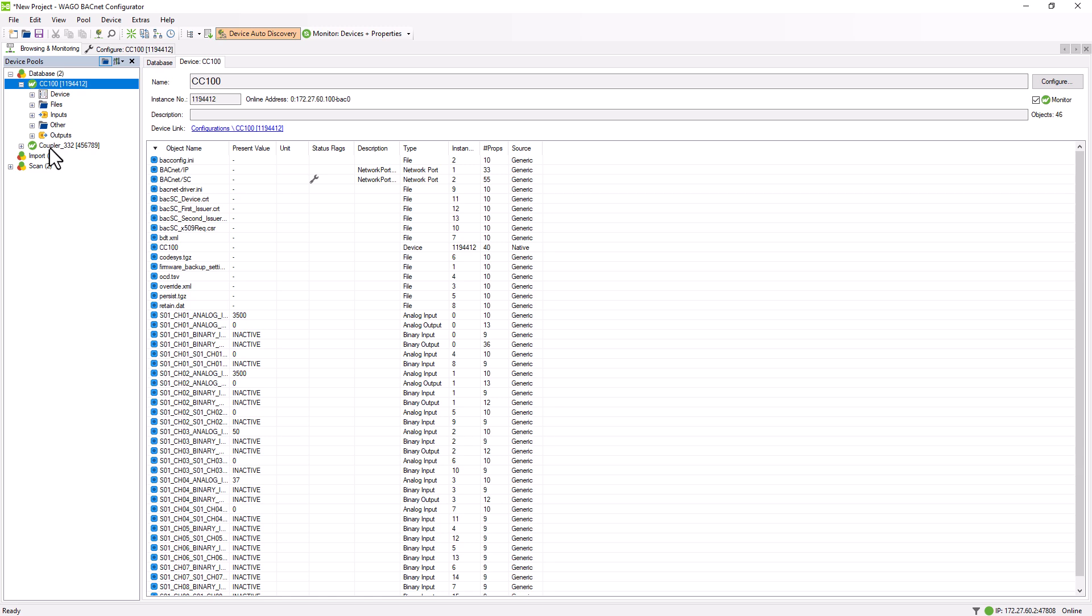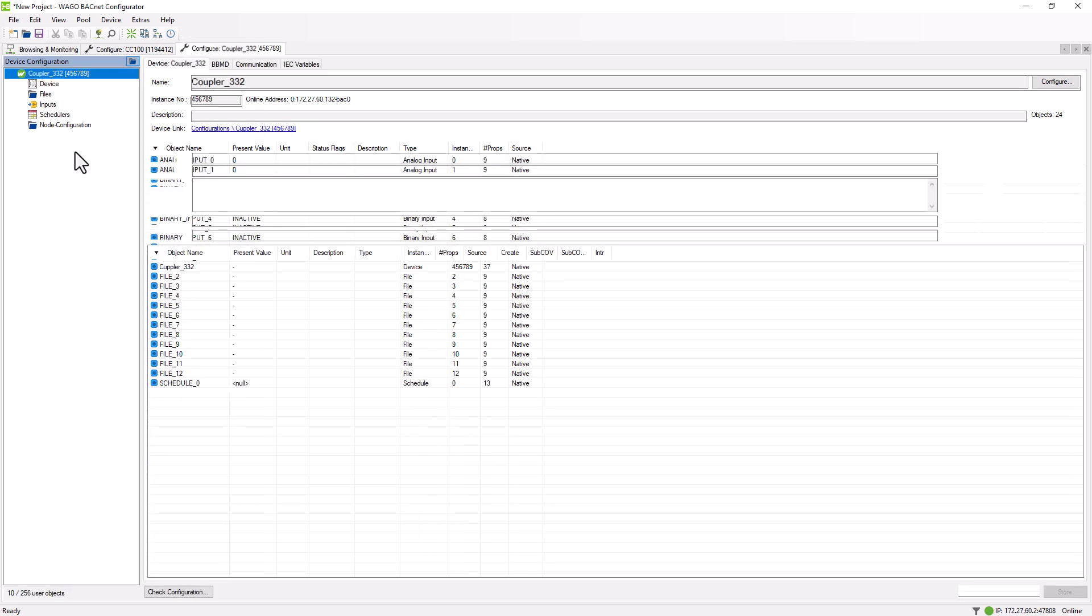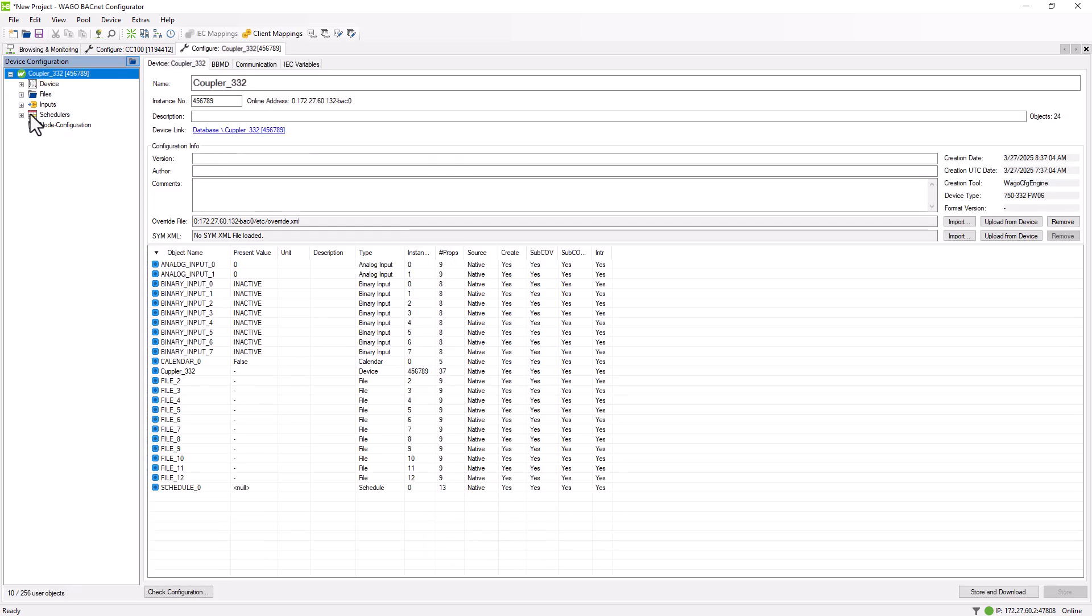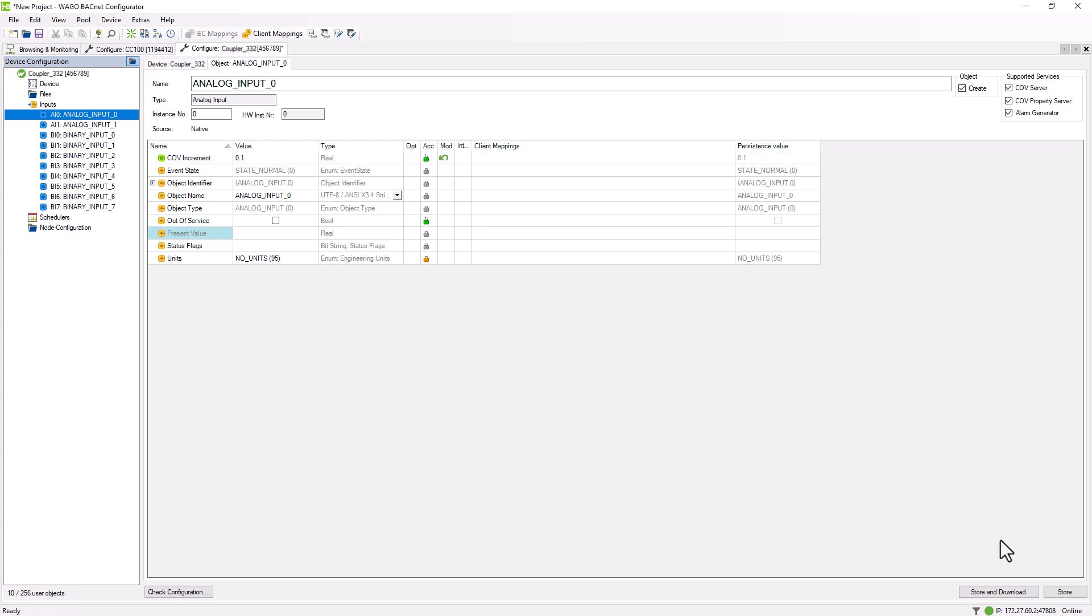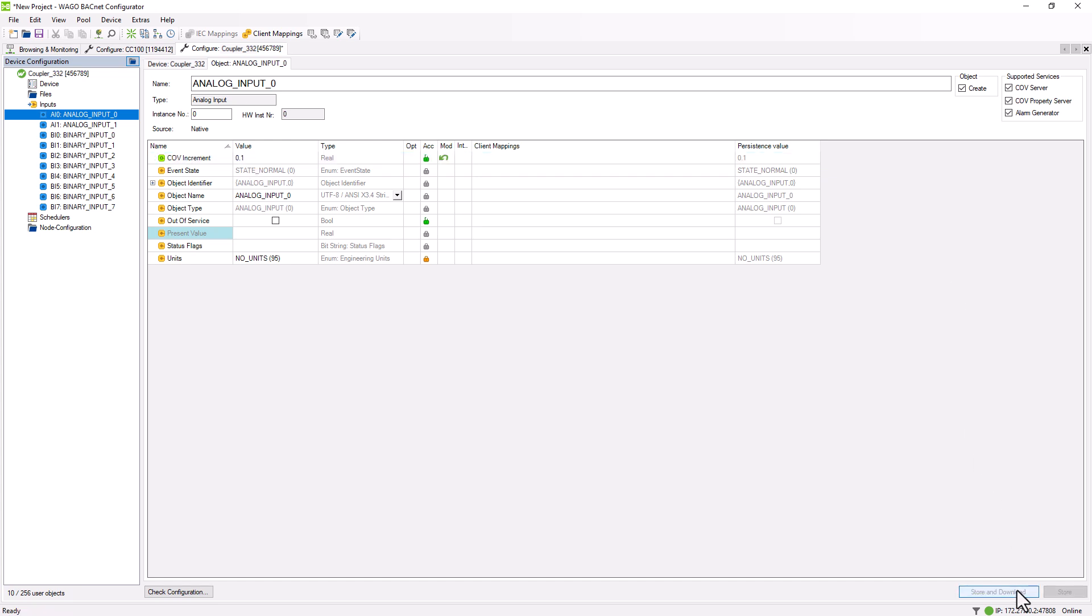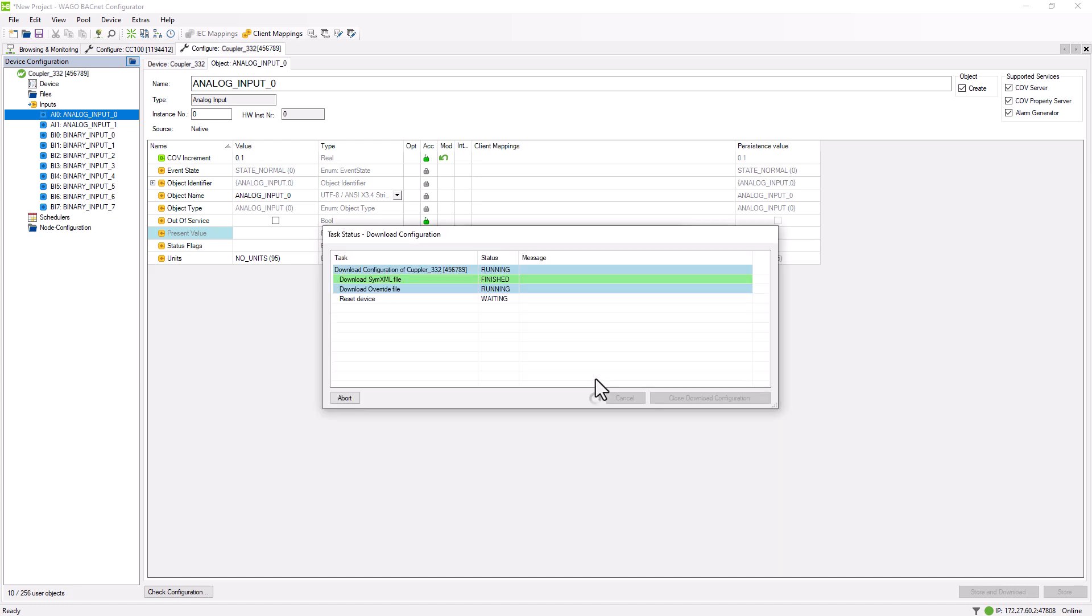The threshold for the Read function is set on the server, in our case, the coupler. Under Inputs, Analog Inputs, we find the property COV increment. Here we can specify, for example, a value of 0.1, meaning the value change must be at least 0.1 before being sent to the CC100 that has subscribed to this value.